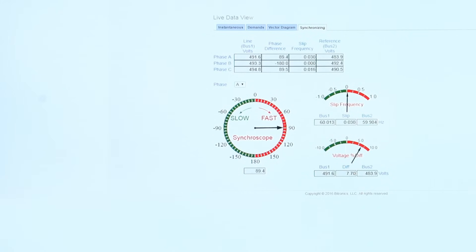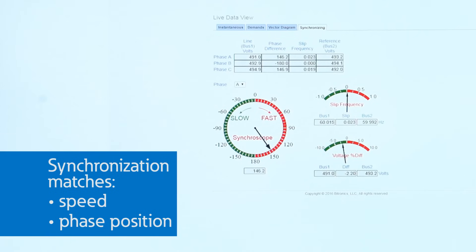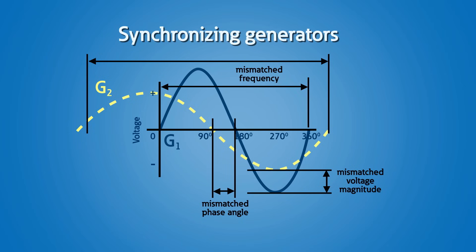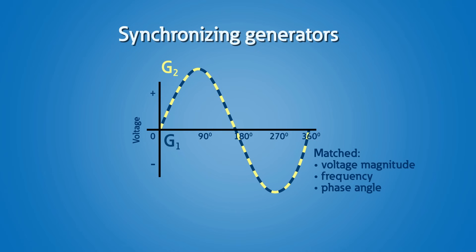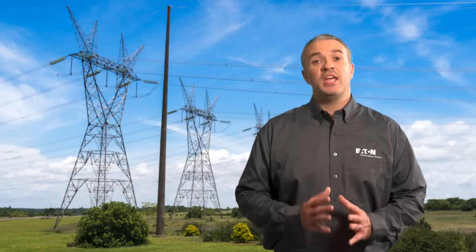The objective of synchronization is to match speed and phase position, so there is little or no transfer of energy when paralleling multiple units or connecting to an existing grid. Synchronizing requires matching voltage magnitudes, frequency, and phase angle. On systems with commercial or industrial generators, synchronizing requires a special transfer switch with that capability.